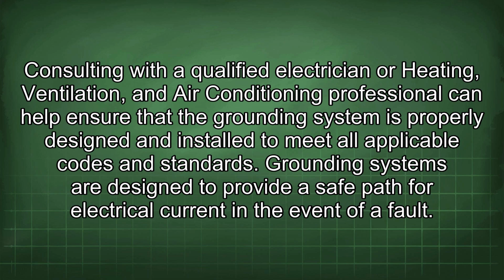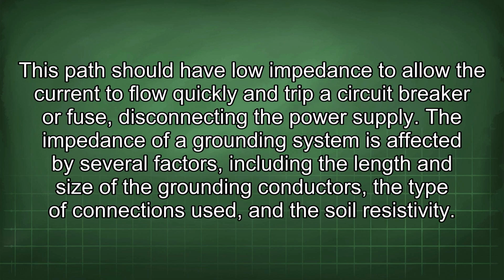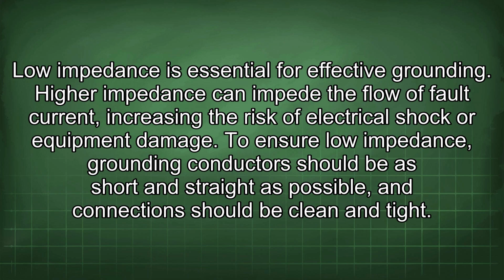Grounding systems are designed to provide a safe path for electrical current in the event of a fault. This path should have low impedance to allow the current to flow quickly and trip a circuit breaker or fuse, disconnecting the power supply. The impedance of a grounding system is affected by several factors, including the length and size of the grounding conductors, the type of connections used, and the soil resistivity. Low impedance is essential for effective grounding. Higher impedance can impede the flow of fault current, increasing the risk of electrical shock or equipment damage.